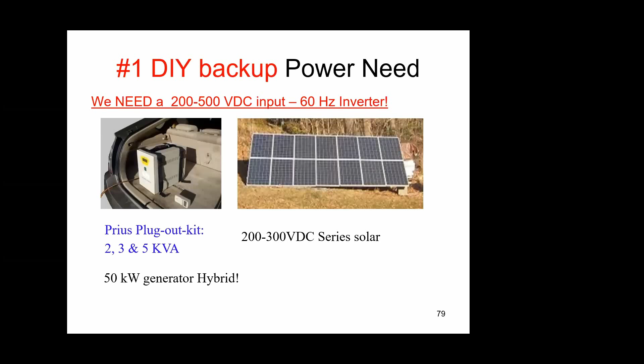Although the nameplate data will say 800 to 1,000 watts, that has to include the amperage for the strip heaters that come on for defrosting. During grid down, power out conditions, you really don't need defrosting. Of course, the defroster will kick on automatically and trip your 1,000 watt inverter, but as soon as it trips, you just cycle the power on that inverter and keep operating — the refrigerator won't try to defrost again for another 8 days or whatever it is.